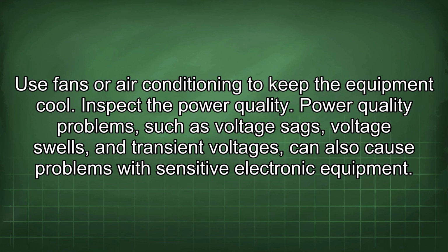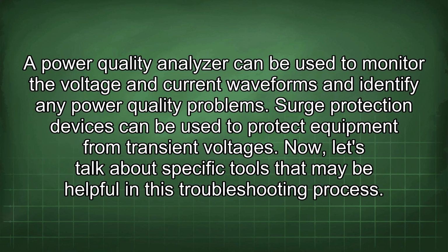Inspect the power quality. Power quality problems such as voltage sags, voltage swells, and transient voltages can also cause problems with sensitive electronic equipment. A power quality analyzer can be used to monitor the voltage and current waveforms and identify any power quality problems. Surge protection devices can be used to protect equipment from transient voltages.